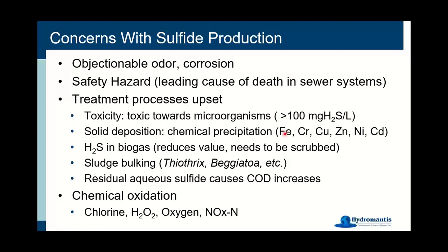Hydrogen sulfide is a key problem observable in wastewater treatment plants. Due to sulfate reduction or sulfide present in incoming wastewater, typical problems include odor, corrosion, and safety hazards — at high enough concentrations it can be lethal. Hydrogen sulfide exhibits toxicity that can interfere with other biological processes. It can also precipitate with iron or heavy metals, leading to solid deposition. In anaerobic digesters, the presence of H₂S in biogas reduces its energy value and must be removed before energy recovery.